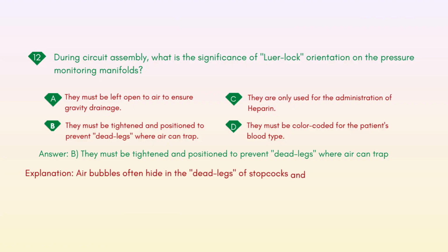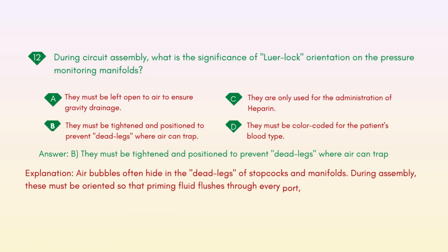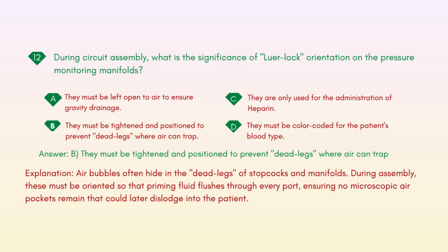Explanation: air bubbles often hide in the dead legs of stopcocks and manifolds. During assembly, these must be oriented so that priming fluid flushes through every port, ensuring no microscopic air pockets remain that could later dislodge into the patient.